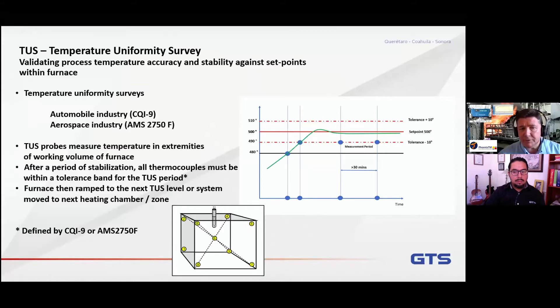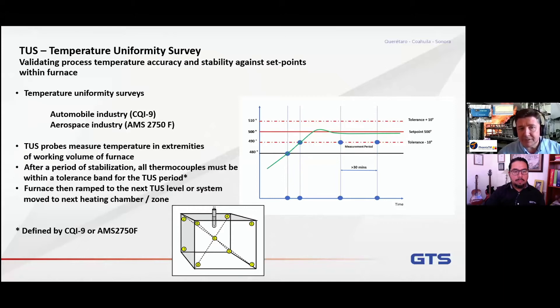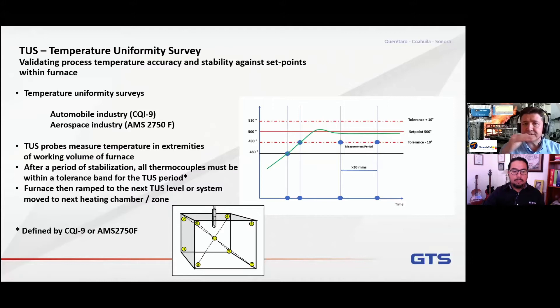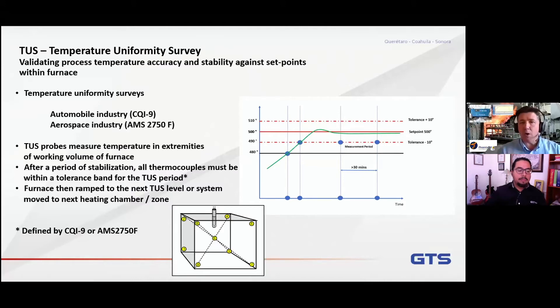So what we're trying to do is, in the volume of the furnace — and if we're talking about a batch furnace, that's generally, in most cases, a cube in form — we're measuring over the working volume of the furnace, the cavity of the furnace, using thermocouples to make sure that we are achieving the correct set point temperature for our heat treatment process. And that temperature is within a tolerance band specified by the standard, and it's stable because it's no good being within tolerance for a short period and then coming out of tolerance and going back in. It needs to be stable over the designated period of time for the survey.